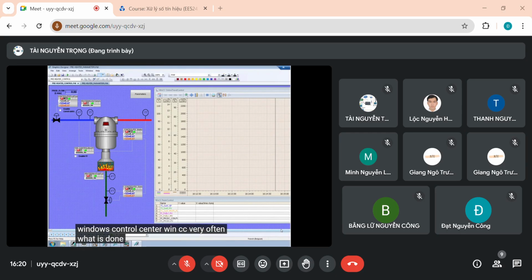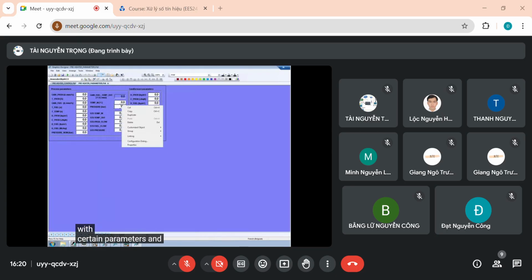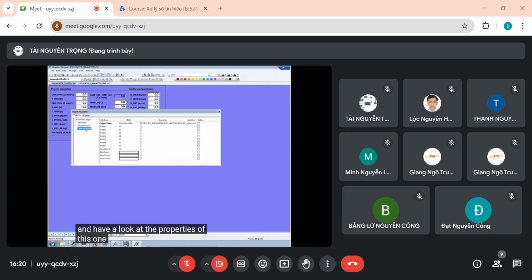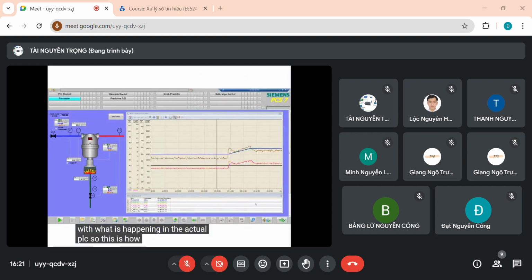Very often what is done is that there is a drawing of the P&ID so that the operator can see where he is interacting with the system, and usually faceplates are used, I will show you later, to interact, for instance, with the PID controls. There are curves and there are possibilities to interact with certain parameters. And if I go and have a look at the properties of this one, you will see here that there is a link with a variable that has been obtained using this compilation procedure. This is how you make the link with what is happening in the actual PLC. So this is how it looks like in real life in the human-machine interface.